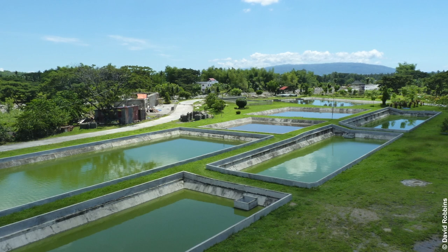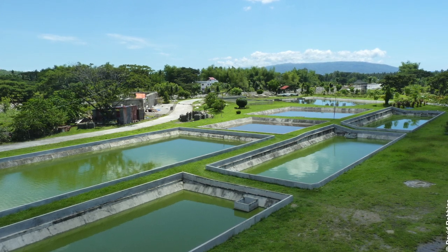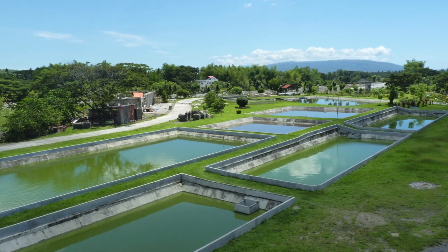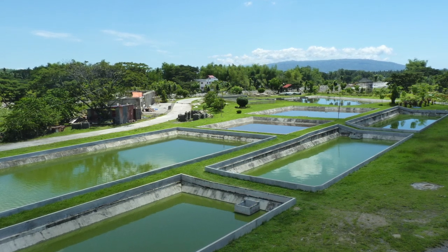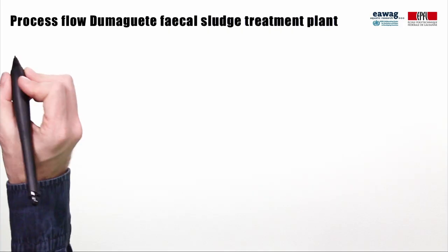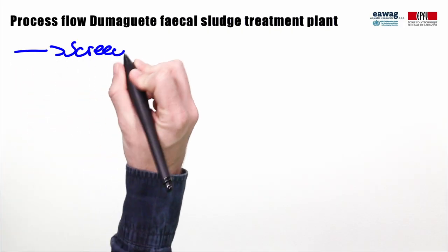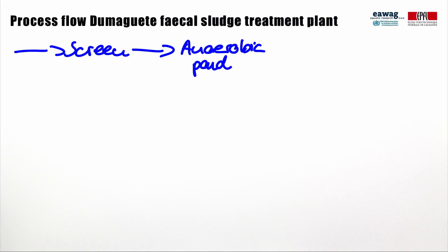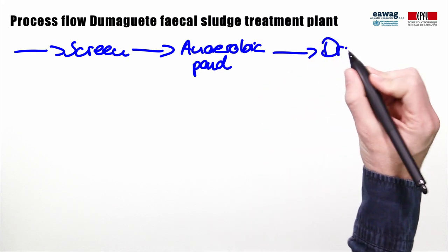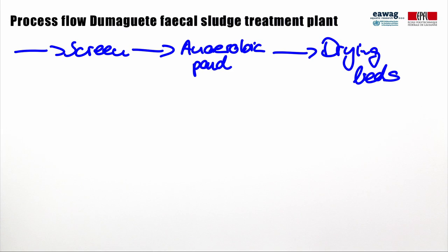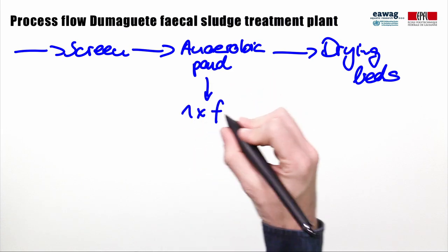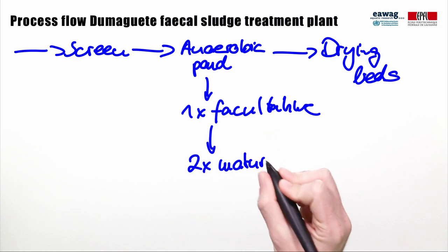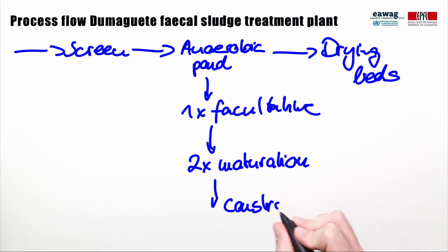This picture shows the fecal sludge treatment plant in Dumaguete, the Philippines. Dumaguete has a treatment capacity of 80 cubic meters of fecal sludge, which is mainly collected from septic tanks by vacuum trucks. Following a screen, solids and liquids are separated in one anaerobic waste stabilization pond. Solids are then dewatered on drying beds. The treatment chain for the liquid effluent includes one facultative pond, two maturation ponds in series, and then a constructed wetland prior to discharge.